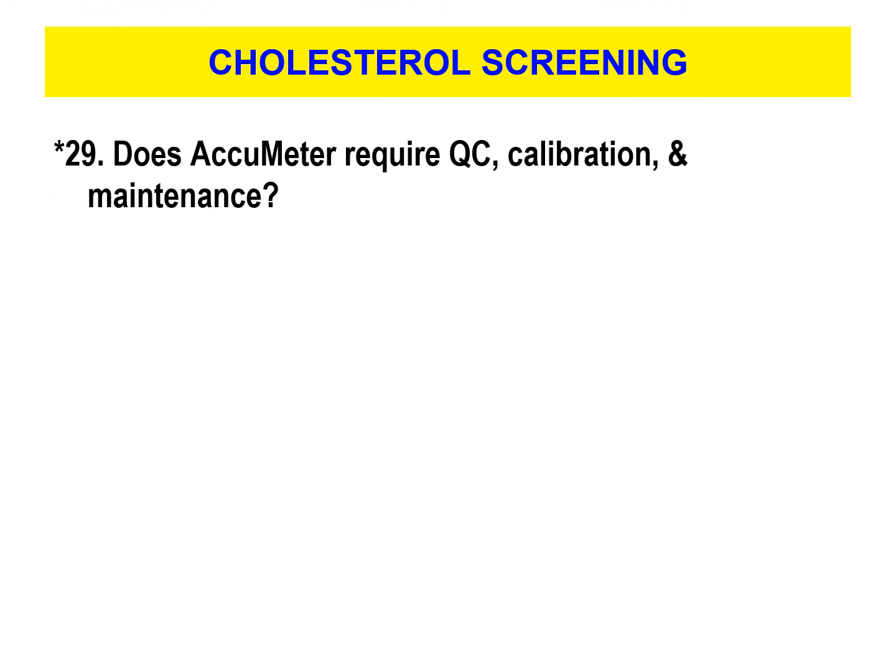Now, if that Accumeter, does it require QC calibration and maintenance? No, because like I said earlier on the slide before, it is not an instrument, right? So if it's not an actual instrument, it may have some type of built-in QC. Some of them do, some of them don't. Again, you want to read the package insert that comes with it and follow the directions. And you also want to follow them to a T. And if it has a built-in QC, you want to make sure that is done properly.